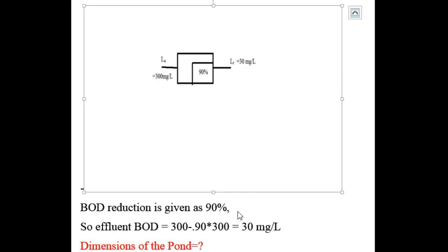Since BOD reduction is 90%, we find the effluent BOD. The inlet BOD is 300 mg per liter, and 90% is being reduced. So effluent BOD = 300 minus 90% of 300 = 30 mg per liter.